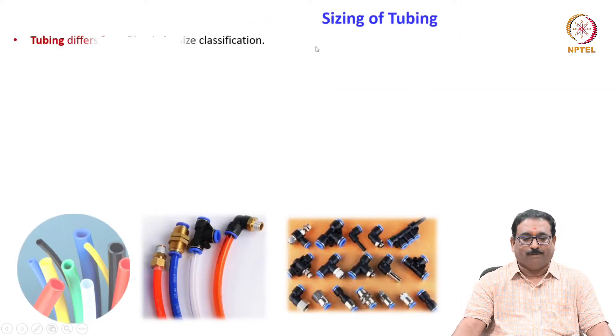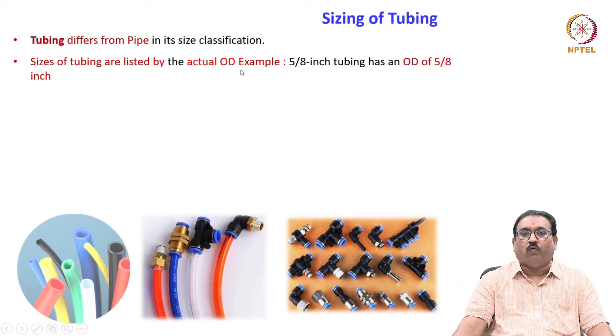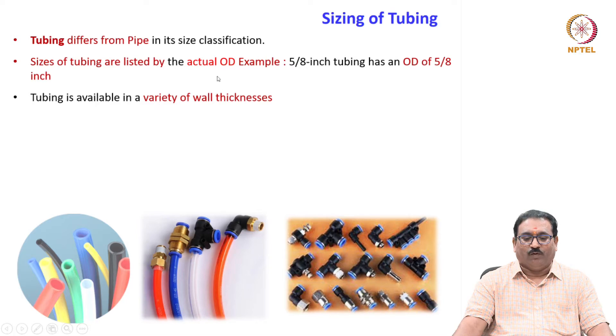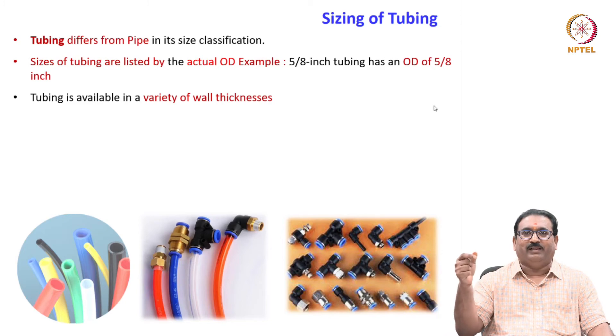Sizing of tubes differs from pipe size classification. Tubes are listed by their actual outside diameter (OD). For example, 5/8-inch tubing has an OD of 5/8 inch. Tubing is available in a variety of wall thicknesses; for example, 5/8-inch OD has various thicknesses under that category, as shown in the next slide.